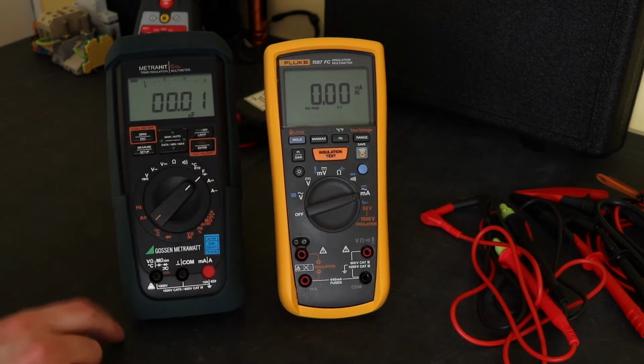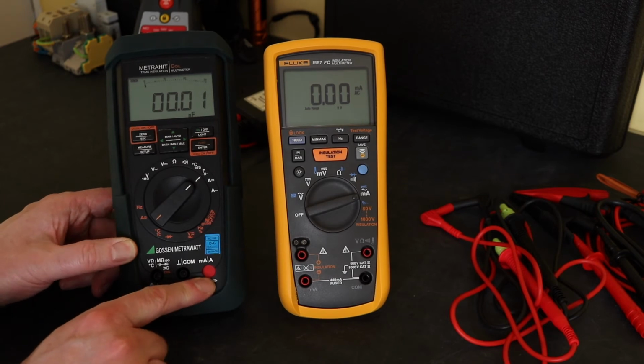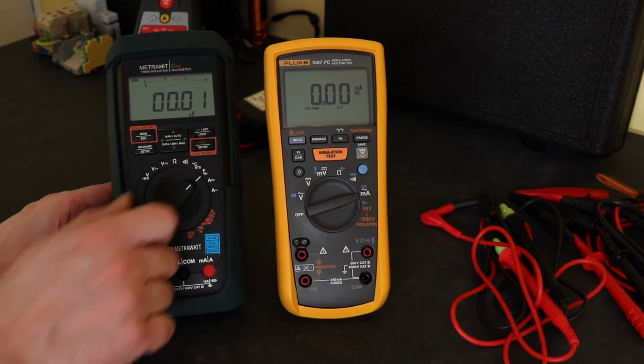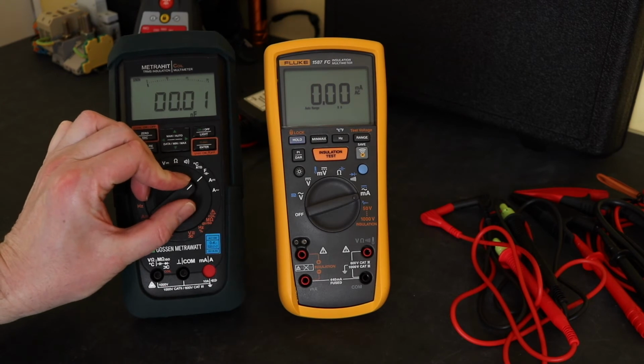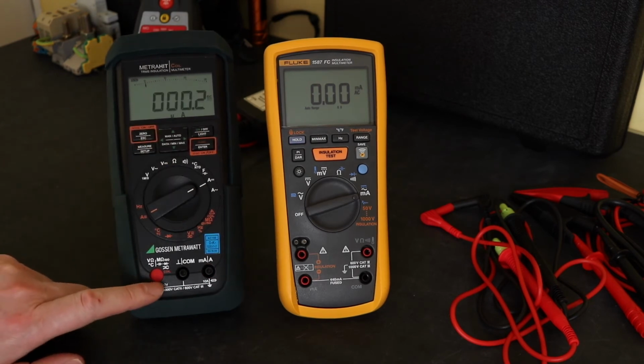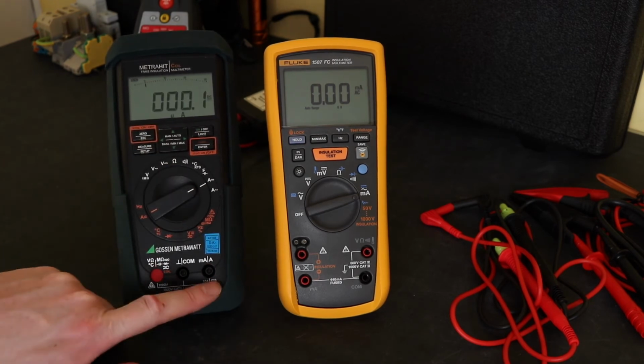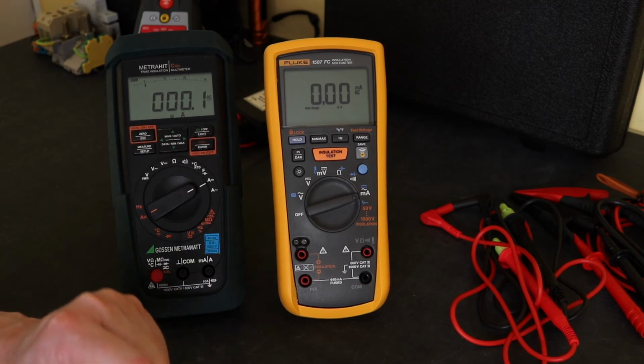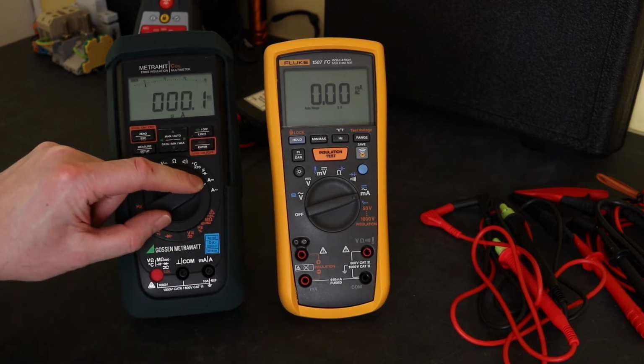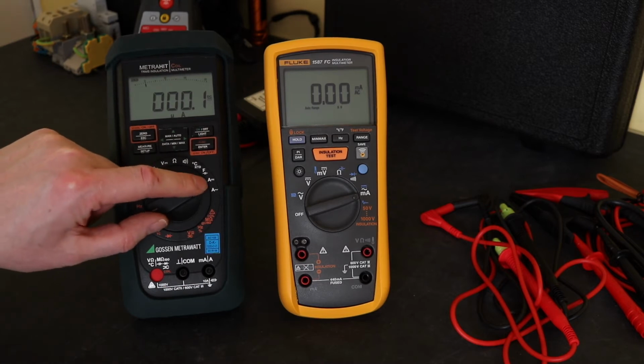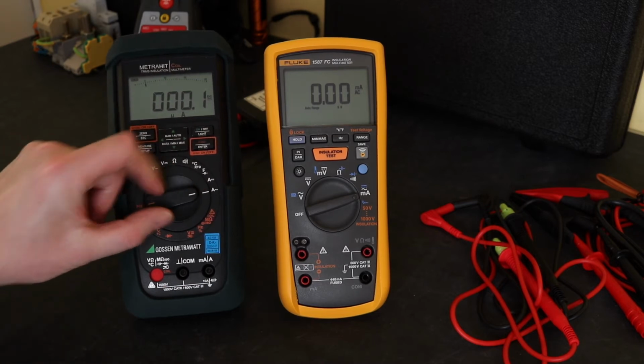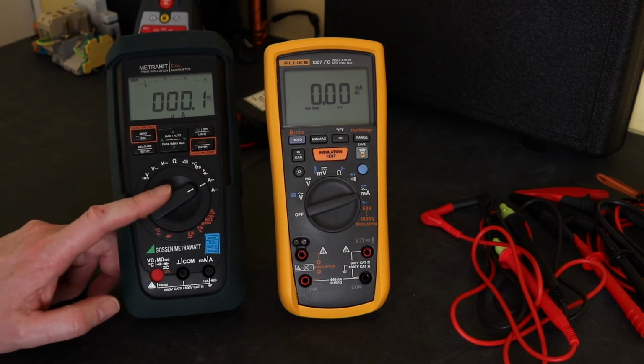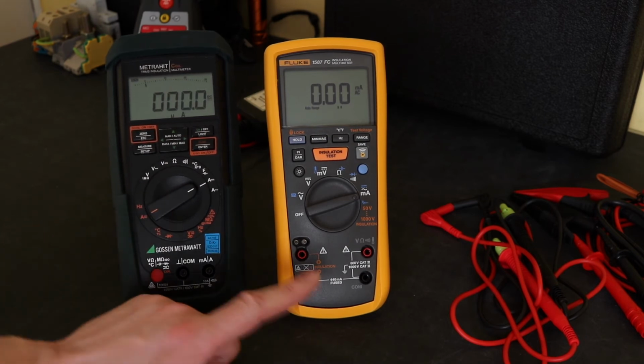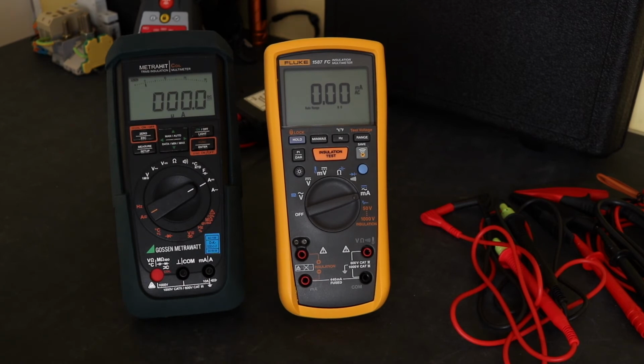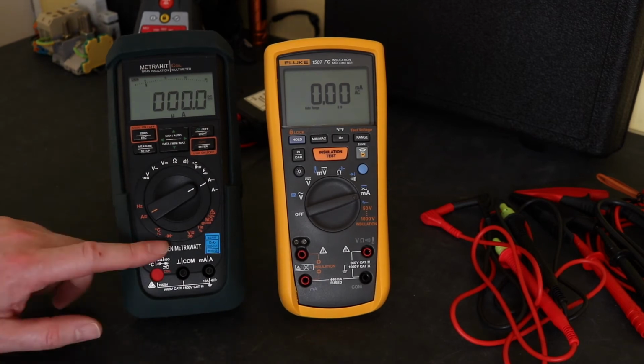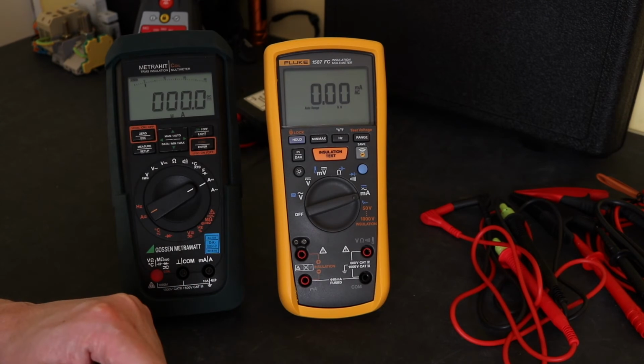For the Gossen Metrawatt, I'll keep it here, you see there's a red cover over the milliamp jack here. As soon as I flip this around to amps DC, it flips over and it blocks off the voltage and opens the milliamp input jack there. And we're on separate functions for DC amps and AC amps there. And this will actually go up to 10 amps on AC and DC against the 400 milliamps of the Fluke there. It goes down to 100 nanoamps.